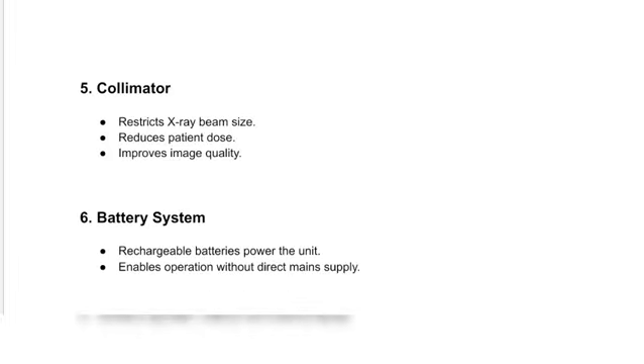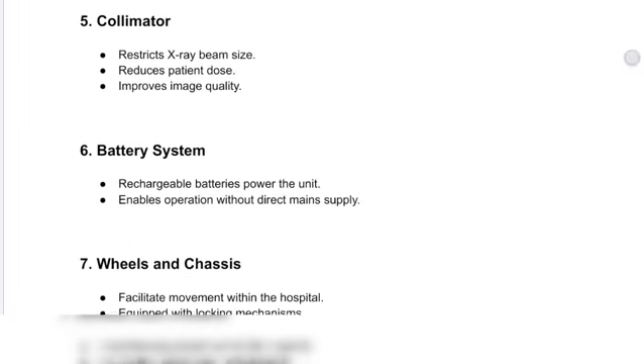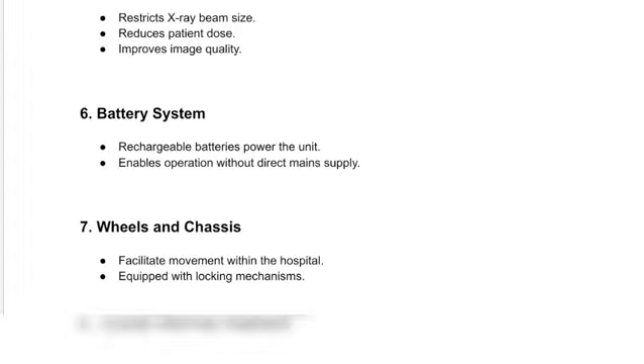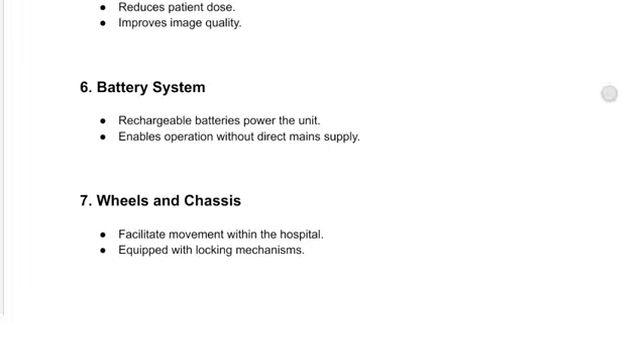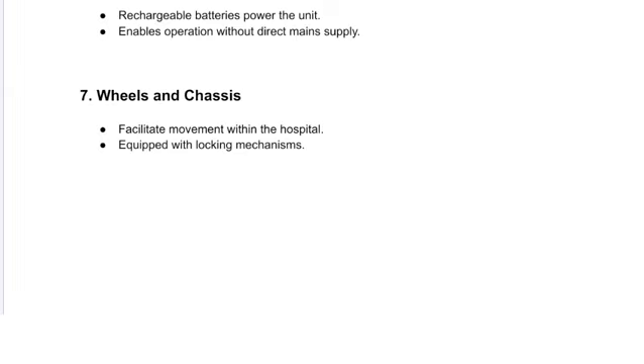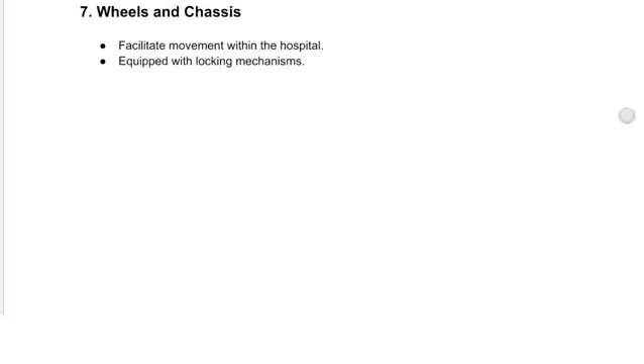Next is the collimator. This collimator restricts the X-ray beam size, reducing the patient dose and improving the image quality. Next is the battery system. Usually we use rechargeable batteries that power the unit. That is, it enables operation without the direct mains supply. Next is wheels and chassis. What are wheels and chassis? They help in the movement of the machine within the hospital. It is equipped with wheels and also a locking mechanism so that we can stop it at the area where it is required.